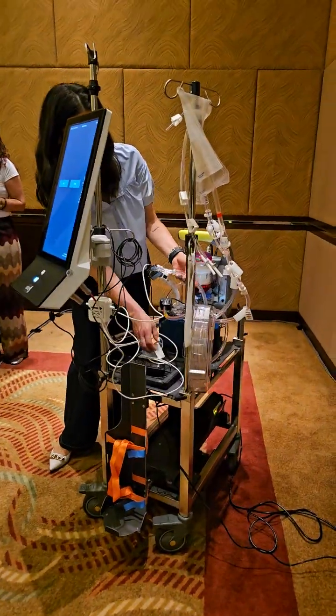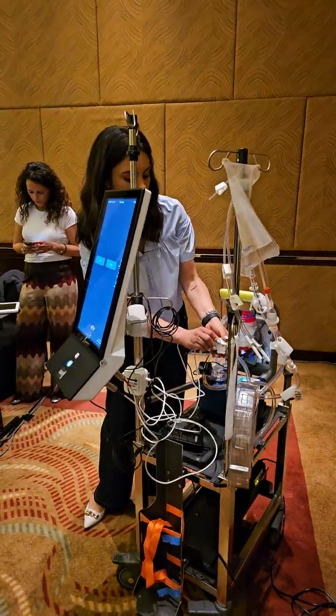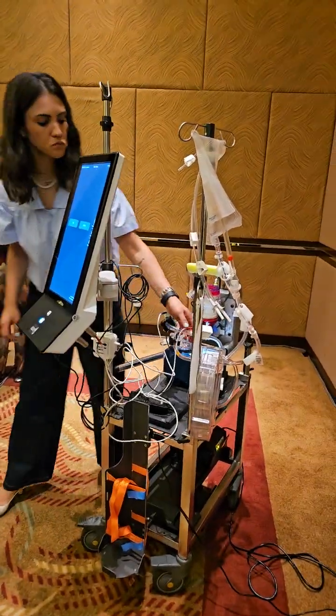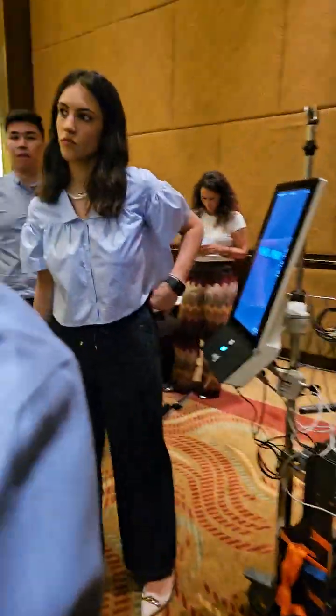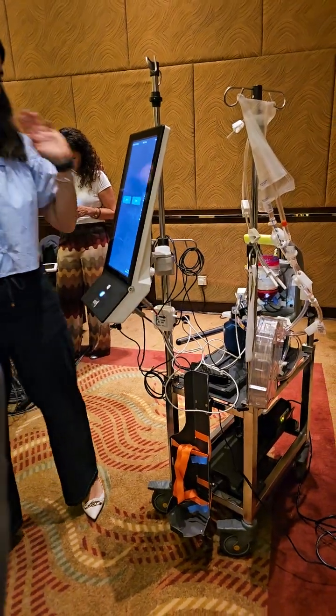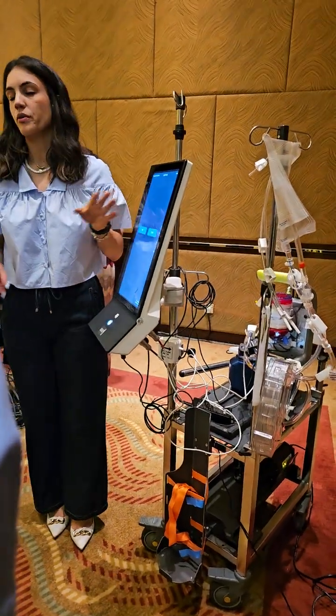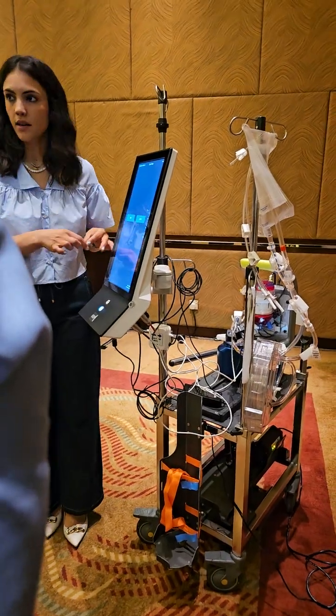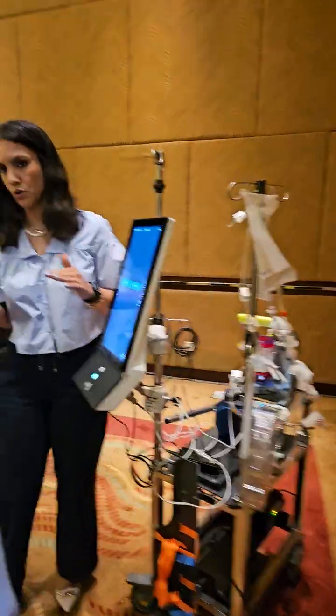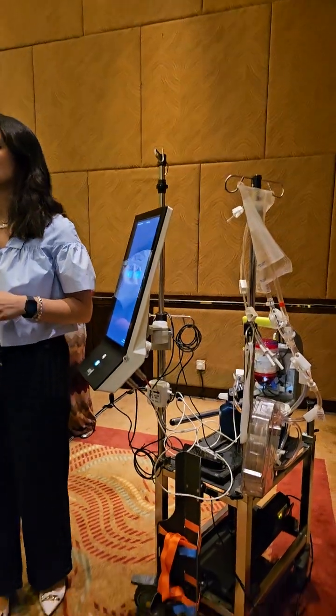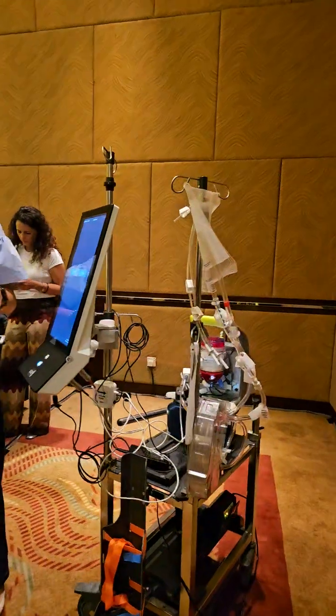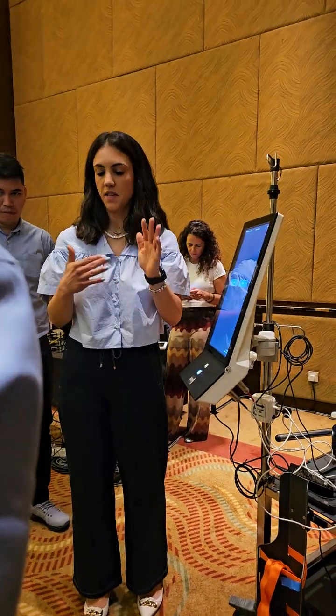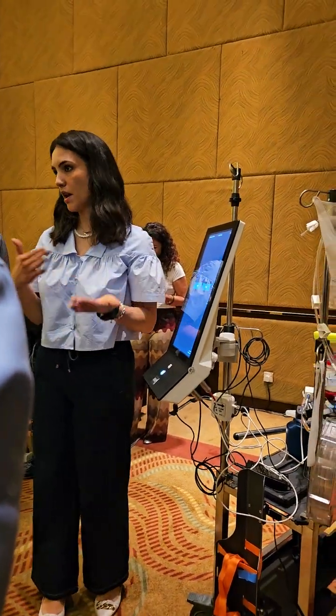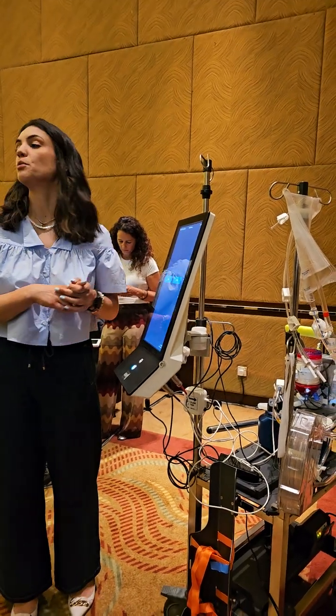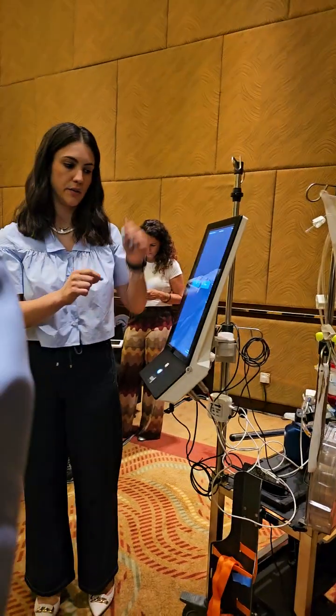Simply put the adapter like this and connect quickly the probe. So is there any difference for using cuvette or not using cuvette? Yes, without the use of cuvette, since you are directly on the tube, you lose a bit of accuracy, but we are talking about 5-6%. And on top of that, if needed, you can adjust and correct the parameters during the procedure. We'll see later on how.